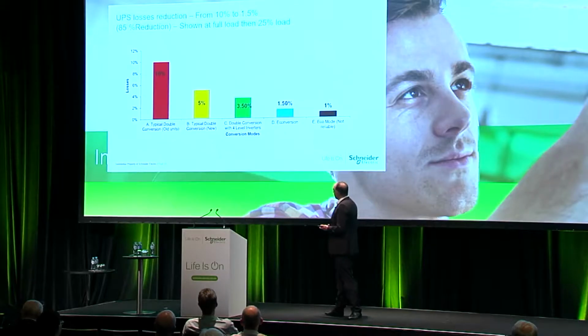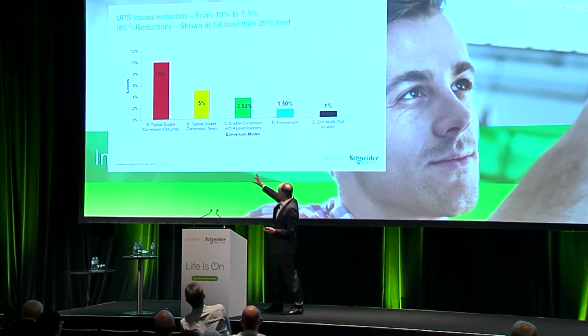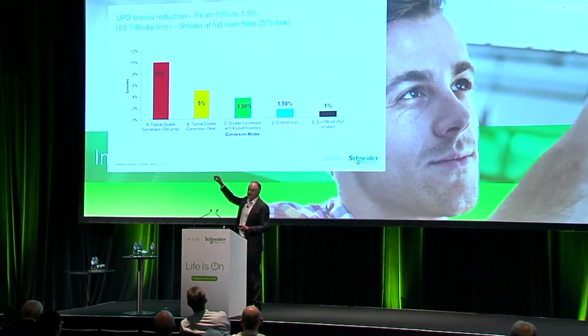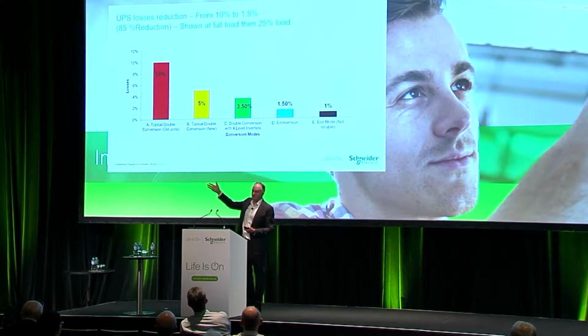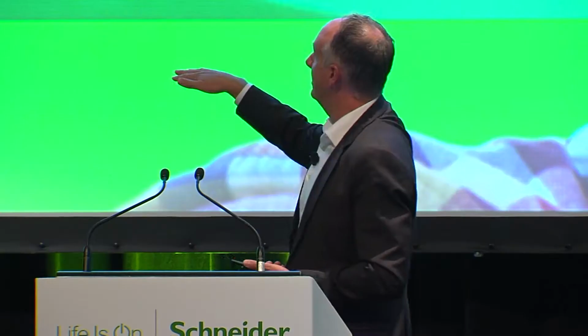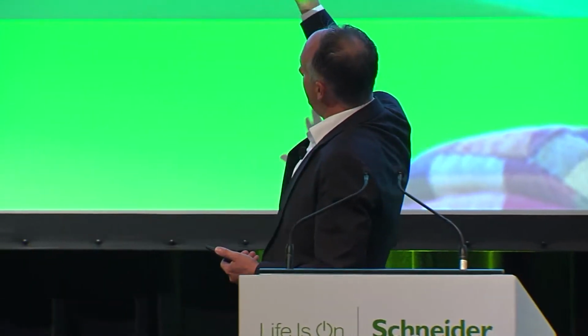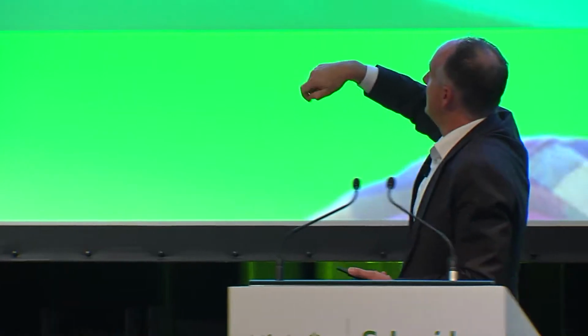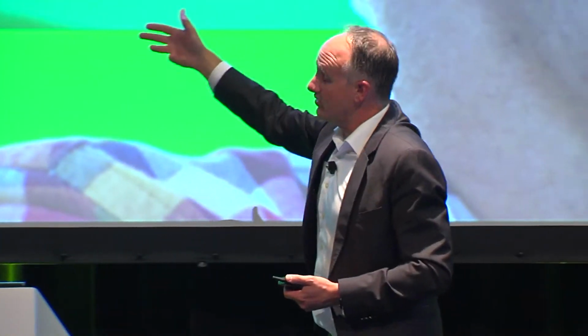So let's take a little bit of a look at efficiency comparison. This is our losses in our UPS power system, and this is at full load. It gets even more aggressively improved as we operate more lightly loaded. So our typical double conversion 2-level inverter has 10% losses at full load, more than that down at the bottom end. The yellow bar is our newer double conversion. That's our 3-level, that most of what Schneider makes.